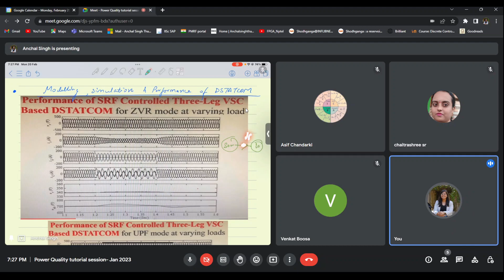If I did not have the compensator in the picture, then all this bad part of the current would have to be supplied by the source. The problem with this is that when this is my source and this is my load, and my source is directly supplying the load, all this bad part of the current would be coming from the source. That means the voltage at the point of common coupling will be highly distorted, because the voltage at the point of common coupling equals Vs minus Is into Zs. Suppose my generator is generating properly at 30 volt. This source impedance is the problem. When it comes into the picture, the voltage at the point of common coupling will be highly distorted because it depends on the Zs magnitude. And if the Is current is non-linear, then the point of common coupling voltage will also become non-linear.